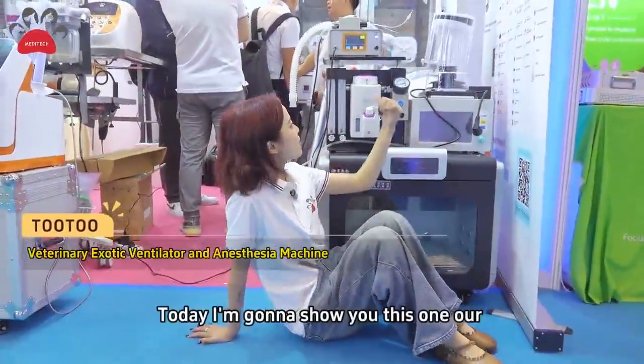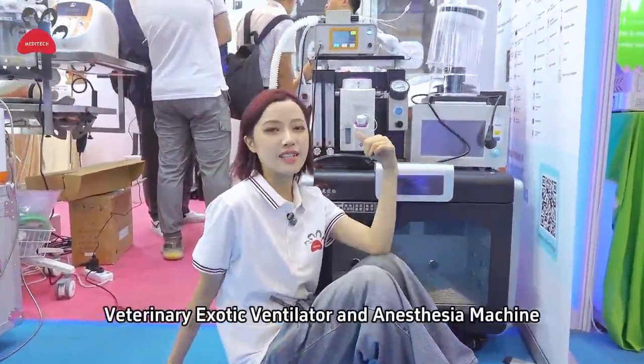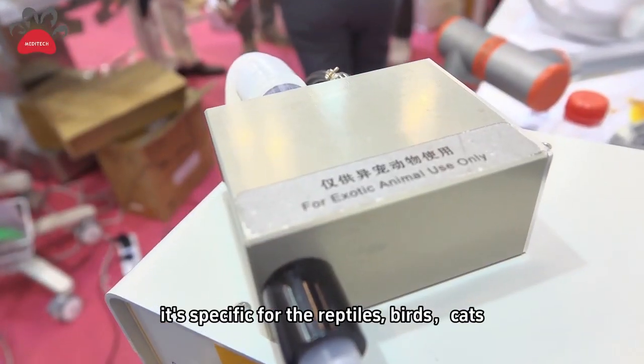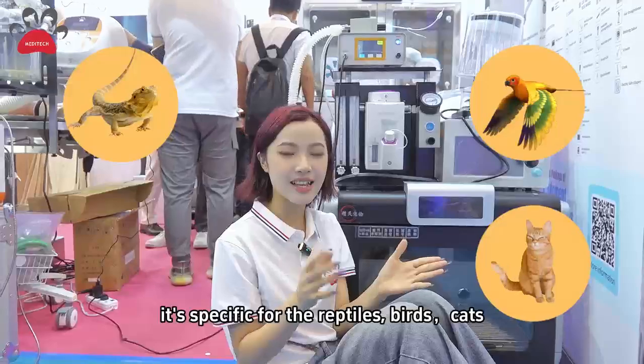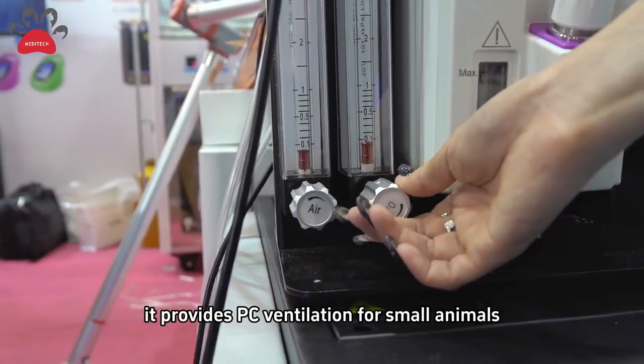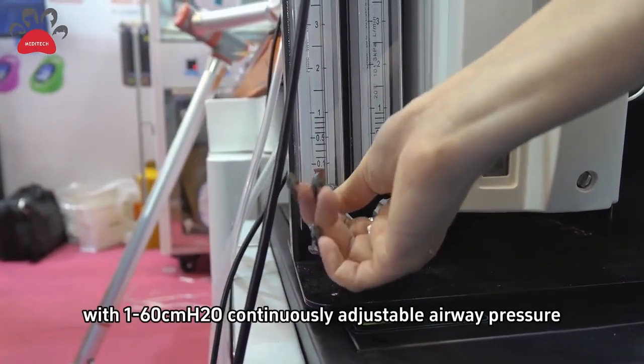Hi folks, this is Rita. Today I want to show you our veterinary exotic ventilator and anesthesia machine. It is specified for reptiles, birds, cats, and small mammals weighing less than 12 kilograms. It provides PC ventilation for small animals with 1 to 60 cmH₂O, continuously adjustable airway pressure.